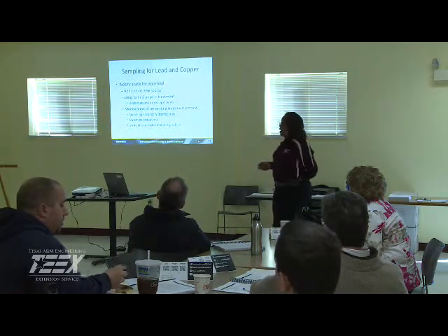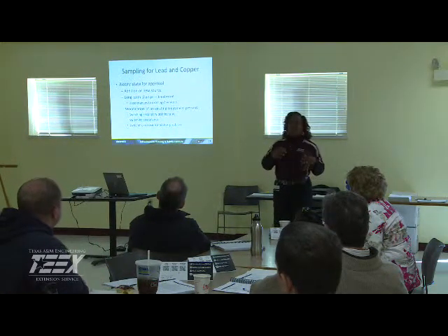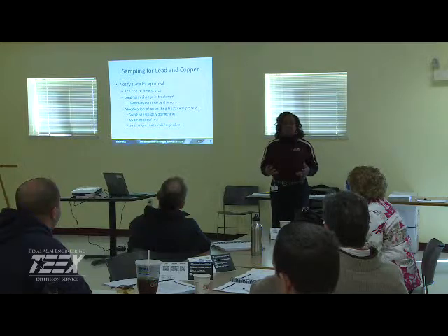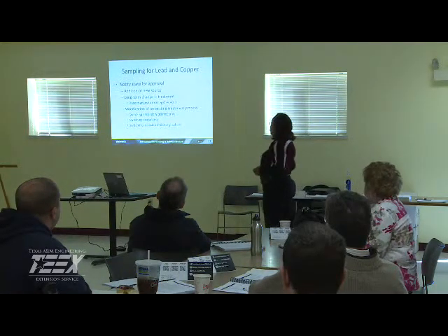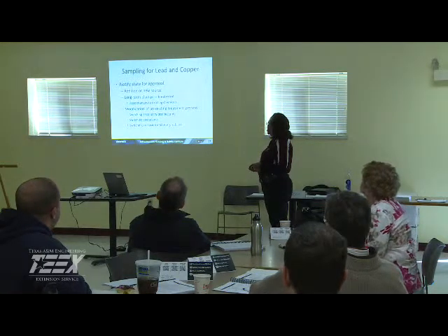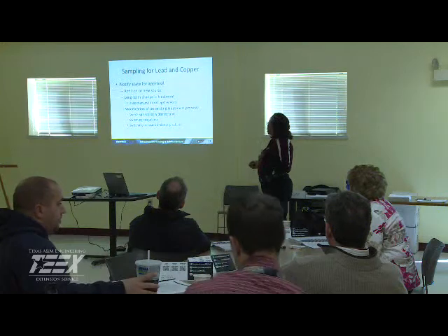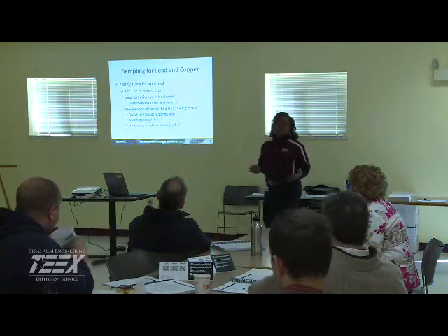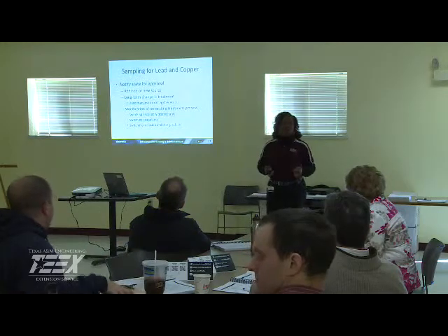If I'm making any type of modification to the treatment scheme, changing chemicals and all of that, it must have that stamp of approval from your primacy agency. So switching secondary disinfectant, coagulant, corrosion inhibitor products, all of that, you need to make sure that you're in direct line of communication with your state agency.